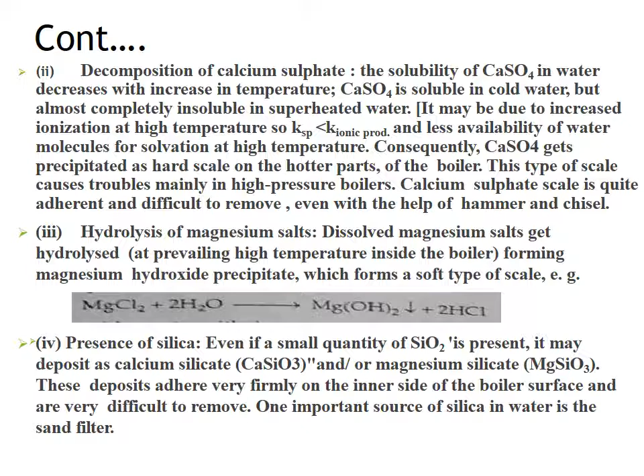If the impurity present in the hard water is silica, even if a small quantity of SiO2 is present, it may deposit as calcium silicate, or it may deposit as magnesium silicate. These deposits adhere very firmly on the inner side of the boiler surface and are very difficult to remove. One important source of silica in water is the sand filter, or simply the sand.